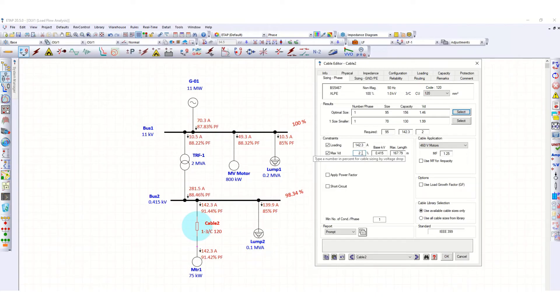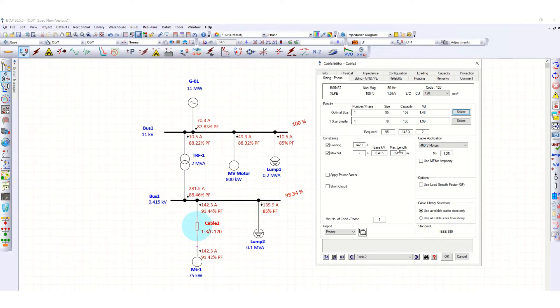The maximum voltage drop is defined as 2%, which is generally the standard — in some projects it may be 3% or another value. The maximum cable length in our case is 100 meters, and at this length the cable can handle up to 167.79 ampere while still fulfilling the voltage drop criteria. Number of conductors per phase is 1.